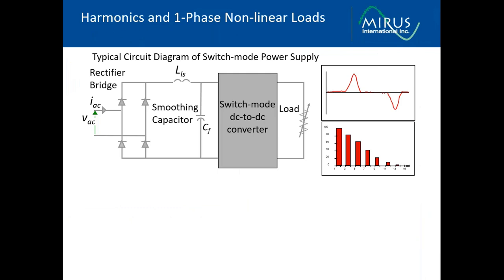So finally, I just want to talk a little bit about single phase, phase to neutral loads. Quite often, parallel active harmonic filters are used to deal with the harmonics generated by single phase, phase to neutral loads. There are passive solutions that are less costly and every bit as effective.